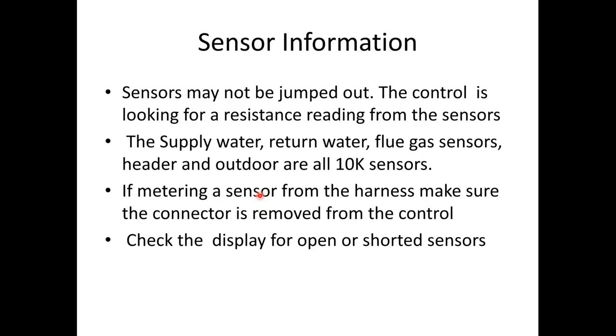If you look at our wiring harnesses, one of the things that really sets us apart, all of our wiring harnesses are labeled. It's written on there what it's doing, where it's going to. There's a lot of wires stuck in there. We have a wiring harness for supply and return sensors, fan speed harnesses, and so on and so on. There's a lot of the same colored wires. We may be telling you to test the blue and gray wire. There's 3 sets of blue and gray wires in there. So we can tell you blue and gray wire that's going to say supply sensor, return sensor, and it tells you where it goes to on the board, like J2, F4 as far as the landing points. Makes troubleshooting much easier.